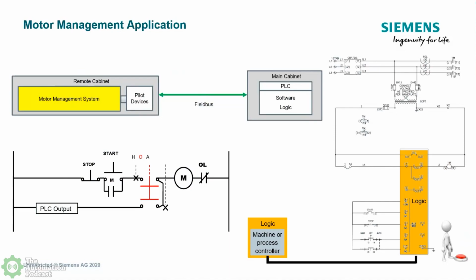You can see you got your control power transformer up here. You're reducing the voltage. You can control and excite the SIMOCODE at 110 to 240 volt. And then again, it has its own 24-volt power supply built in. And we'll show you how that's utilized here in just a few minutes more. But this is the introduction of SIMOCODE into this motor management system that we're showing you. And then again, the field bus, we'll talk about the communication protocols that SIMOCODE can do, with an emphasis today, as you saw on the first slide, on Ethernet IP.